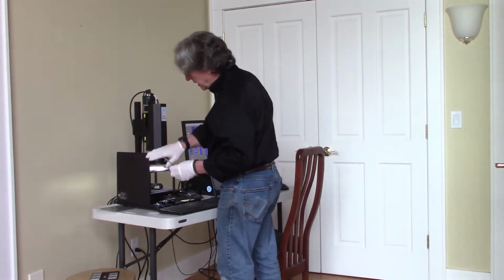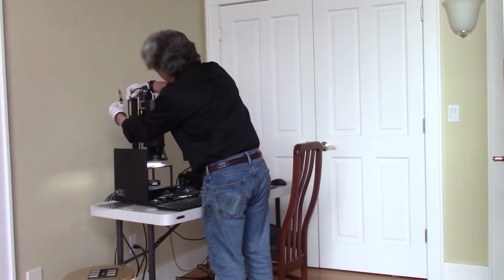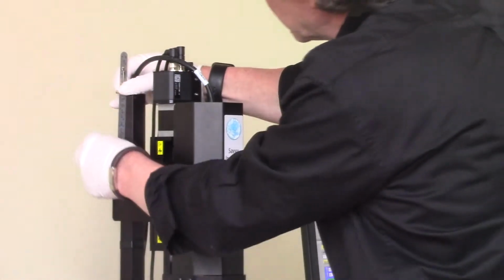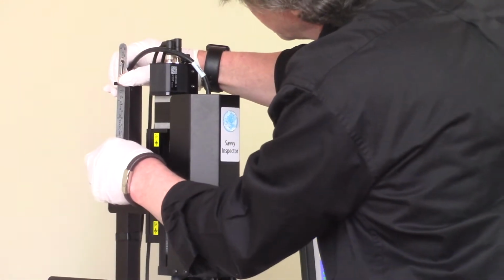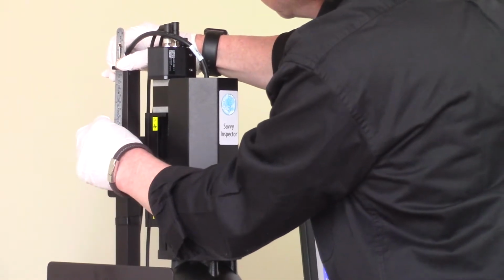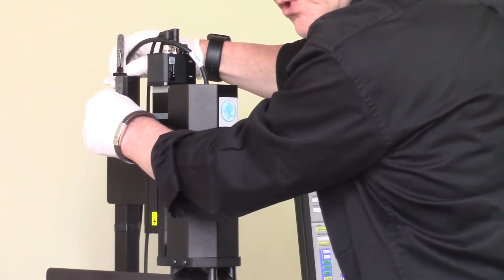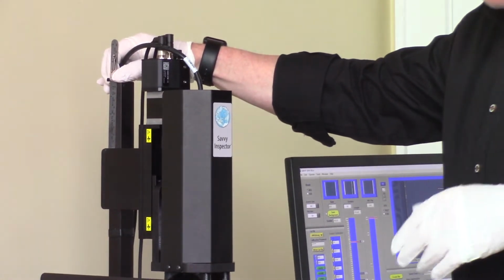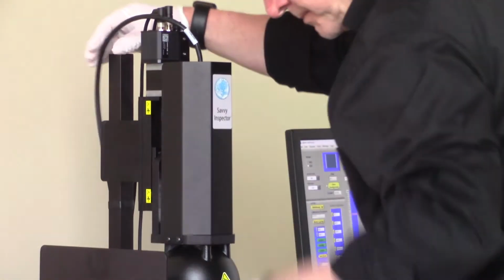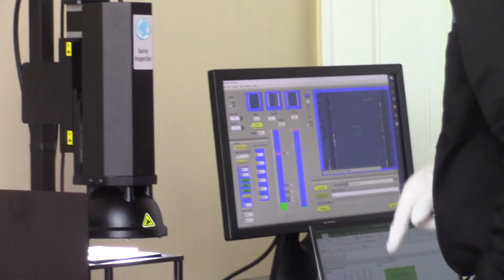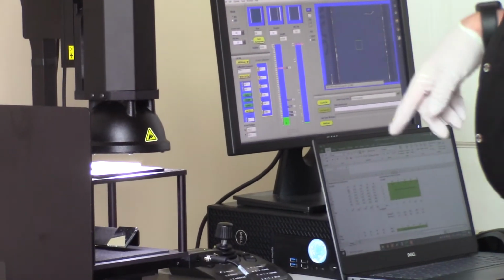First thing you're going to do when you get it out of the box and you get it set up is you're going to set the head height. We have to drop the head in order to ship it. So the first thing you do is make sure that this head height, from the top of the bracket that holds the head to the top of the post that the bracket is mounted on, has to be 96 millimeters plus or minus about a millimeter. Okay? Once you've got your head height set, if it's a motorized system, check your cabling.